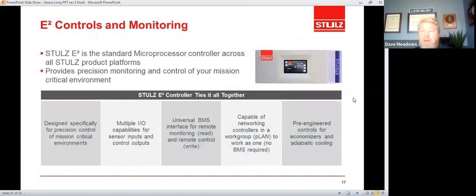Getting close to the end here, all Stulz units are controlled by our E² controller. This is a PLC controller, a programmable logic controller, that is able to communicate to BMS systems through Modbus, BACnet, HTTP, and SNMP protocols. We also offer within the platform a PLAN option, a private local area network, where in the absence of a BMS system, you can link up to 8 units together on the PLAN.